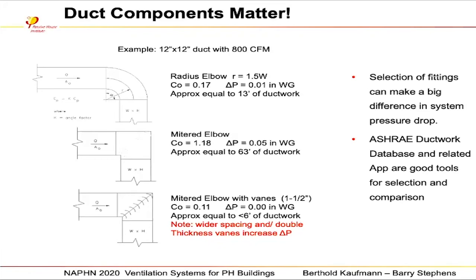You see on the top the equivalent of 13 feet of ductwork for a radius elbow. A mitered elbow with a square, which creates a lot of turbulence, is the equivalent of 63 feet of ductwork. And on the bottom, a mitered elbow with turning vanes reduces that to less than 6 feet of ductwork. So when you choose your components, it really has a huge impact on your system.